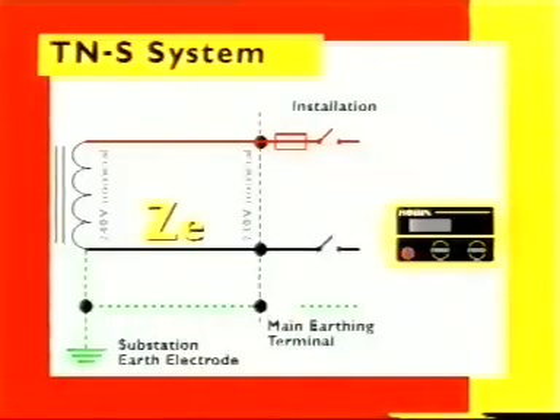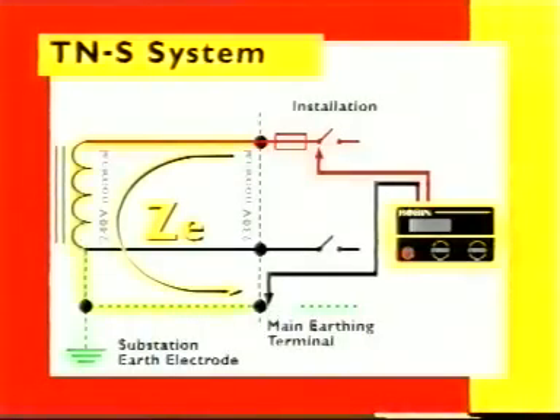First, confirm correct incoming polarity. The network phase earth fault loop impedance, referred to as ZE, is first measured. The supply is effectively isolated to circuits and the test conducted between the means of earthing and an incoming phase conductor.